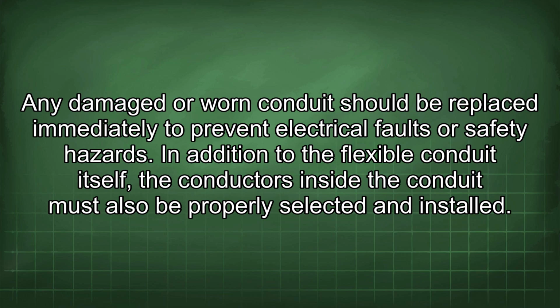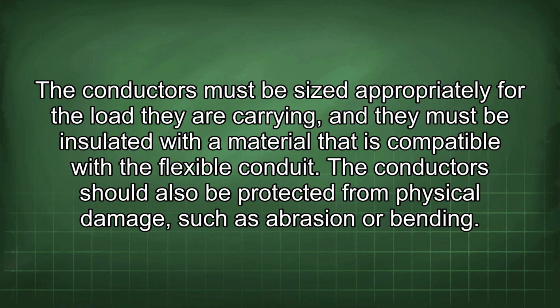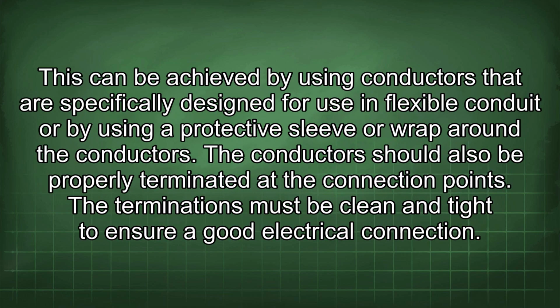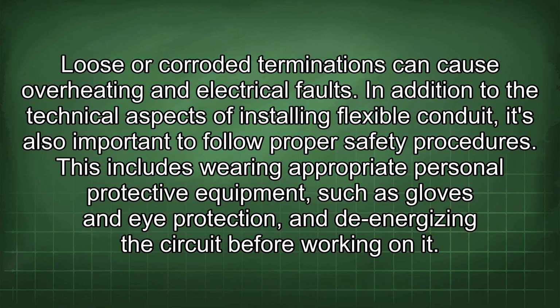In addition to the flexible conduit itself, the conductors inside the conduit must also be properly selected and installed. The conductors must be sized appropriately for the load they are carrying, and they must be insulated with a material that is compatible with the flexible conduit. The conductors should also be protected from physical damage, such as abrasion or bending. This can be achieved by using conductors that are specifically designed for use in flexible conduit or by using a protective sleeve or wrap around the conductors. The conductors should also be properly terminated at the connection points. The terminations must be clean and tight to ensure a good electrical connection. Loose or corroded terminations can cause overheating and electrical faults.